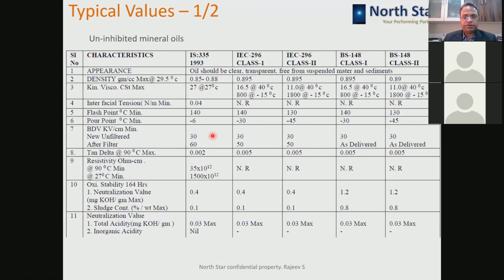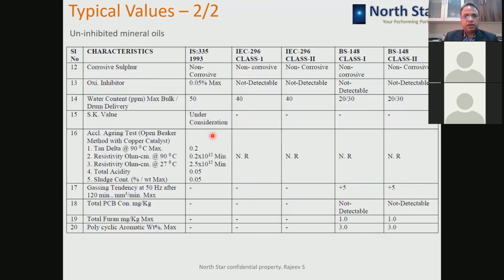So likewise, these values are mentioned in different standards like IS 335, IEC 60296, and likewise. Corrosive sulfur is there, then oxidation inhibitor is there. It should not be more than 0.05% maximum. Water content, again, is 50 ppm. And if the accelerated aging test is performed, then these are the limits given. PCB in all the standards should be nil or non-detectable. For total furan, IS and IEC are silent about it, but British Standard 148 has mentioned some limit, and for polycyclic aromatics, again British Standard mentions some limit, which is not in IEC and IS.